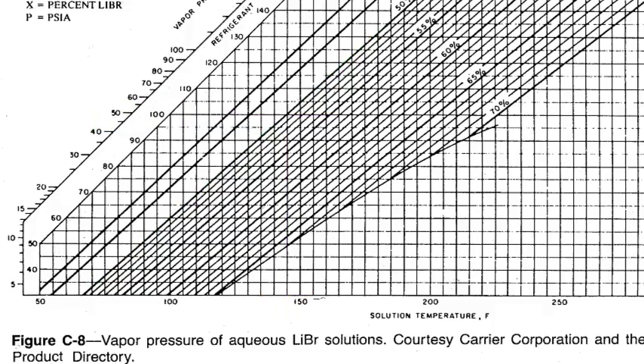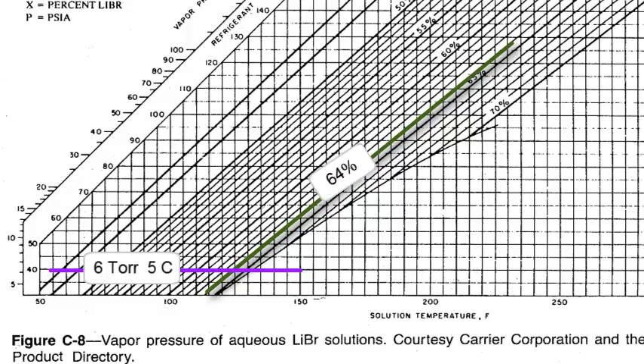In order to make the water in the evaporator boil at 5 degrees C, we need a pressure throughout the evaporator and the absorber of 6 torr. If we choose to use a brine concentration of 64% at the absorber inlet, it must be at 57 degrees C.